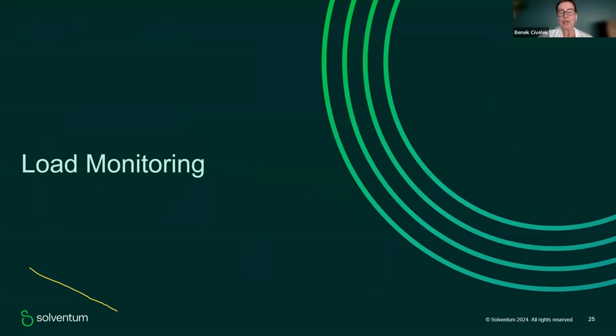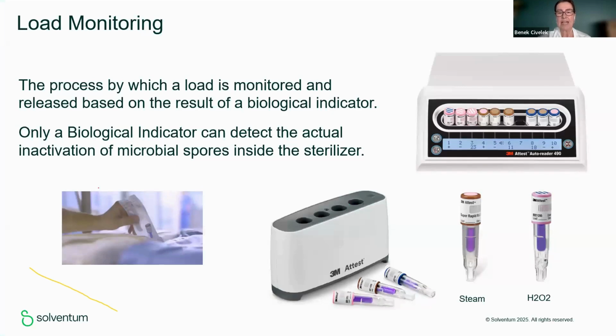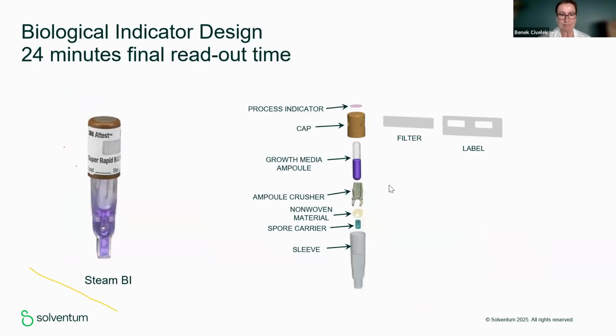When you move to load monitoring, we know that load monitoring is done by a biological indicator, because all the guidelines reference this type of biological indicator, because it is the only actual indicator that can show the inactivation of microbial spores. And we know that there are several available for steam and for hydrogen peroxide, and they have dedicated auto readers, with which you can have the results automatically.